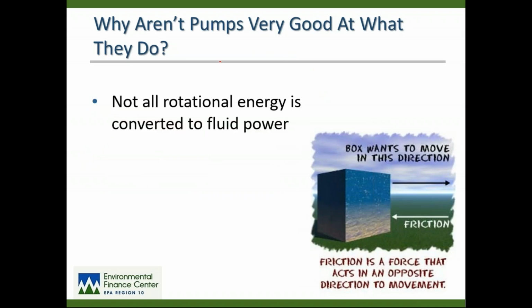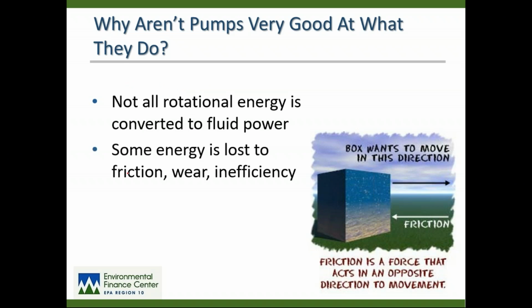Pumps are even worse at what they do. Not all of that rotational energy in the pump is being converted to fluid power. Again, you're going to lose some of that energy to friction, wear, and inefficiency. Inefficiency of the pump as designed. Maybe it wasn't the right pump for the job. Internal wear. A pump only delivers its rated efficiency the day it's brand new and first turned on, and it starts wearing out internally from that point forward.